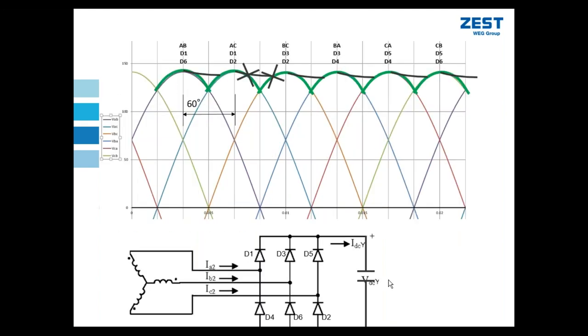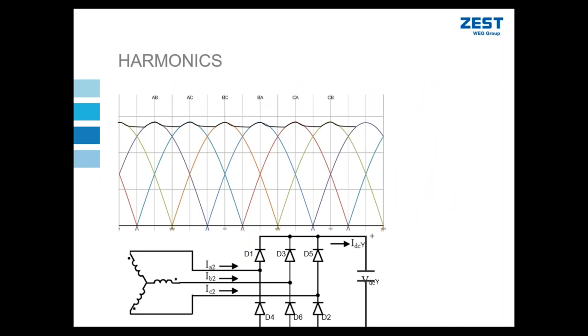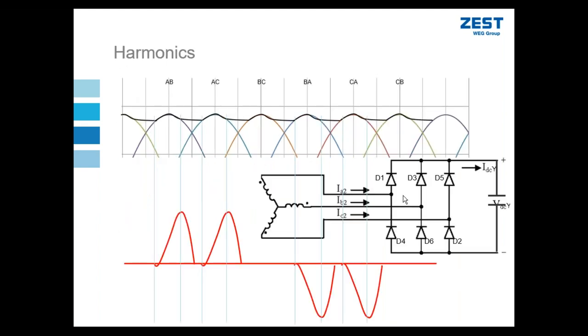So what we've shown here is what the voltage waveform on the DC link at the output of the bridge rectifier will look like. What we're now going to do is have a look at what the current waveform would look like if we were to measure the current in one phase, in this case phase A. Okay, well, let's have a look. We've said that during the period where the phase-to-phase voltage is higher than the capacitor voltage, my energy, in this case in the form of current, is drawn from my supply. That's why during that interval shown in the red, if I measure my current in phase A, I get a peak and it drops off.